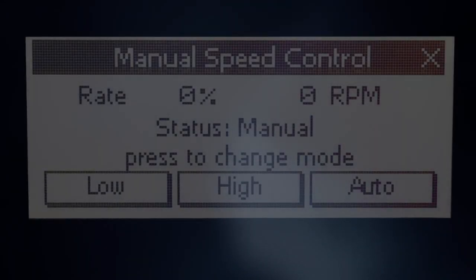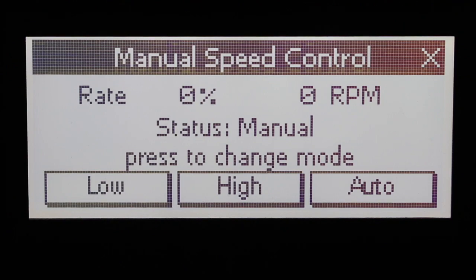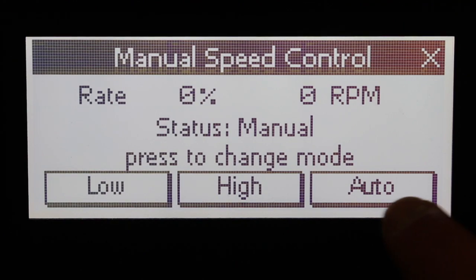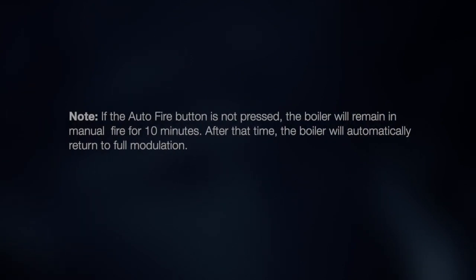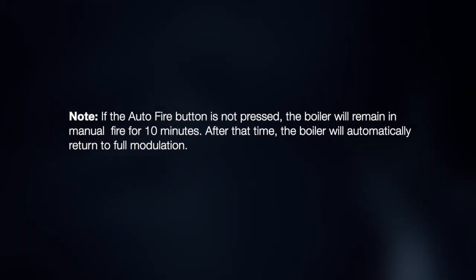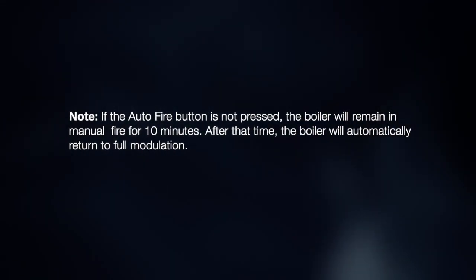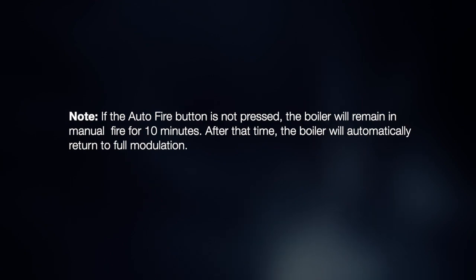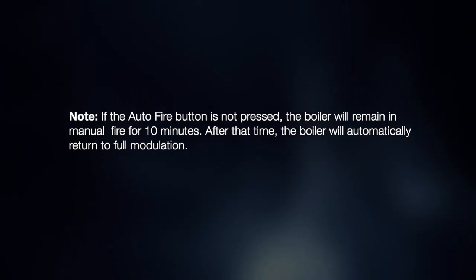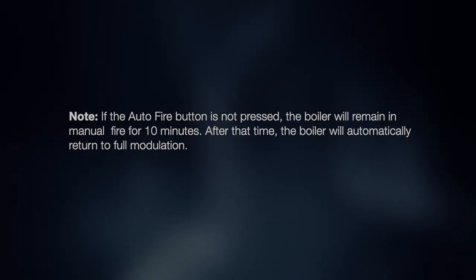Once all testing is completed, return the boiler to automatic modulation by pressing auto-fire on the touch screen display. If the auto-fire button is not pressed, the boiler will remain in manual fire for 10 minutes, after which it will automatically return to full modulation.